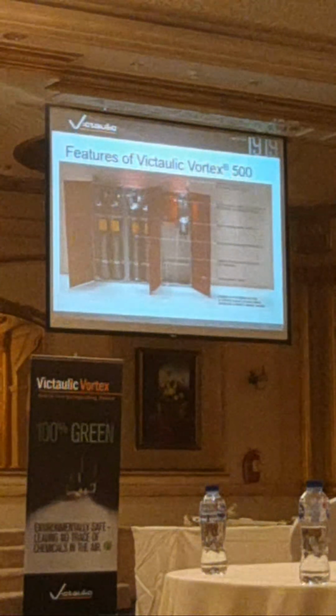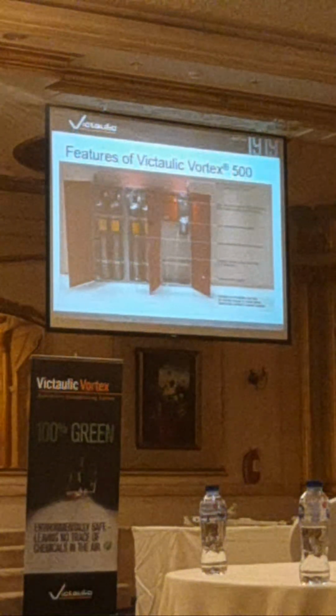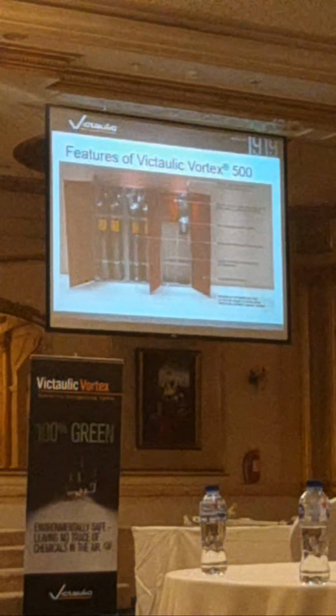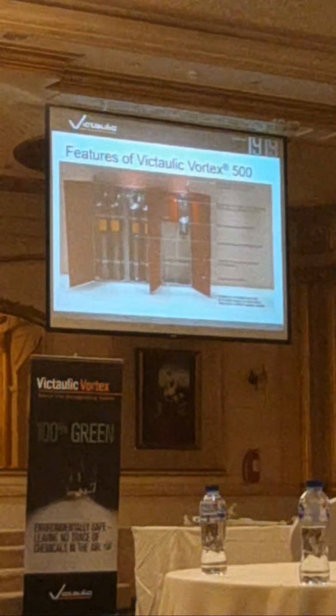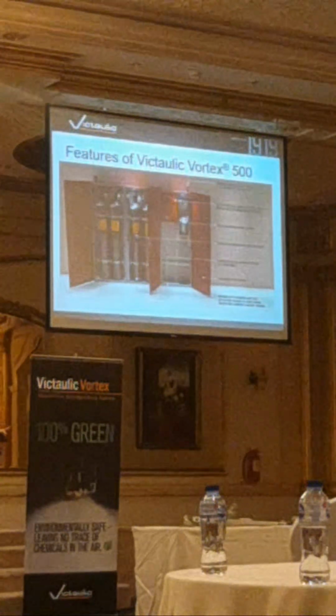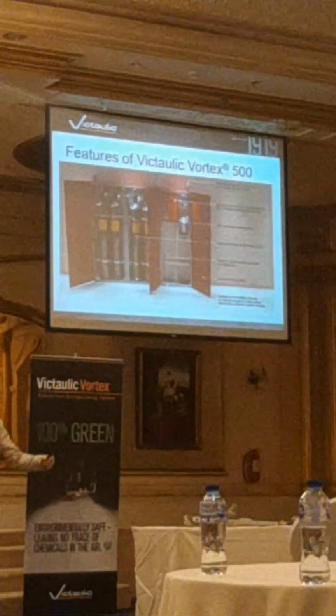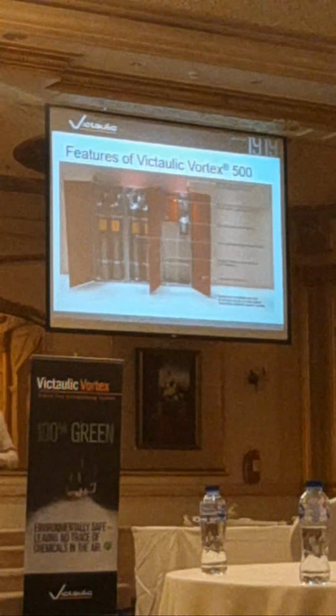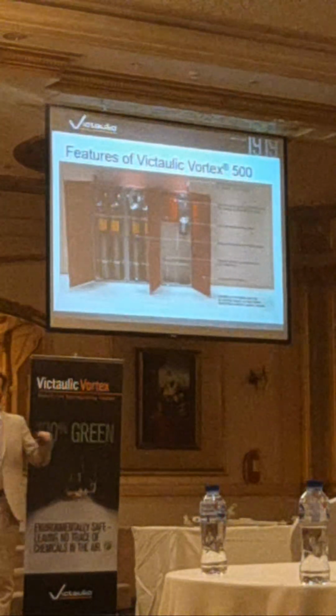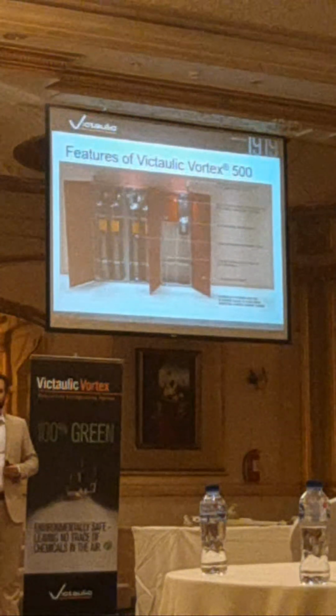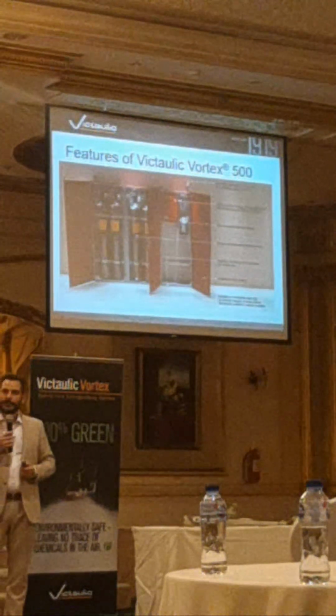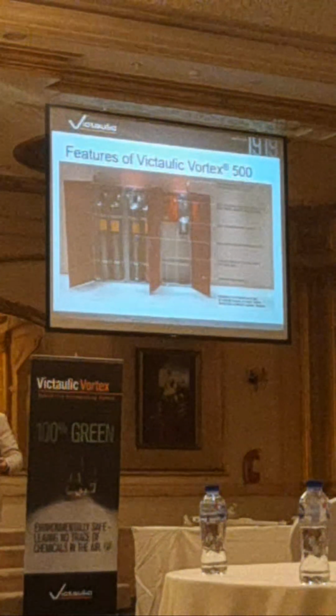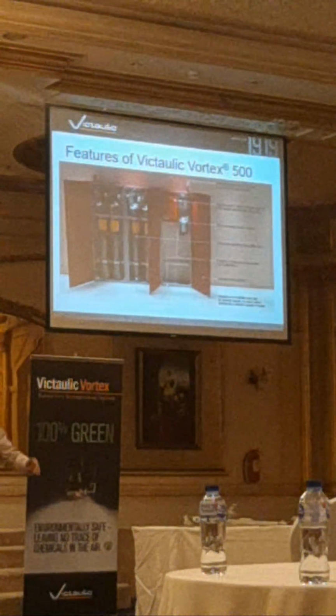What about fire ignition, reignition? Did you consider? Of course, the gas will be there. Similar to an Inergen system, you have your retention time. You have your 10 minutes retention time where your oxygen concentration is on a level where a fire can't reignite anymore. It's not only the water that's doing its job, it's also the gas. So total of that duration, you consider your tank size? Yes. Correct. The amount of water is depending on how long you're discharging, and the standard and the approval is for 3 minutes. So during those 3 minutes, you add the water.